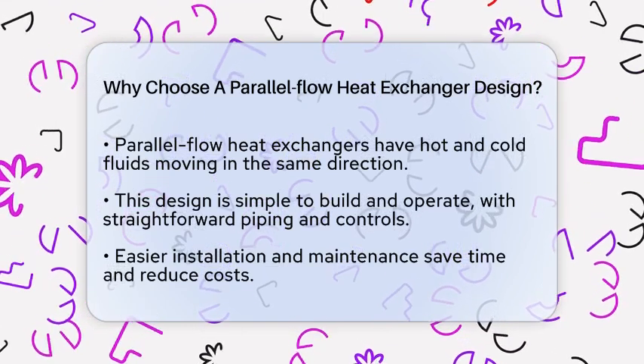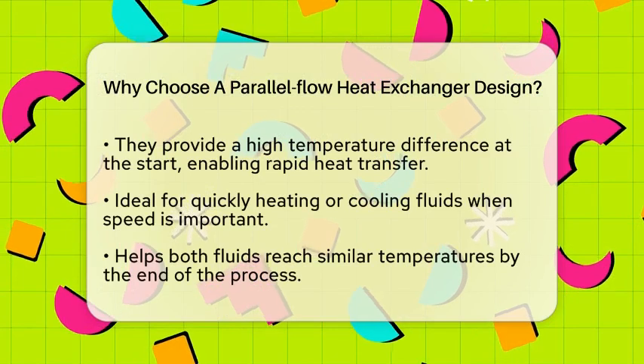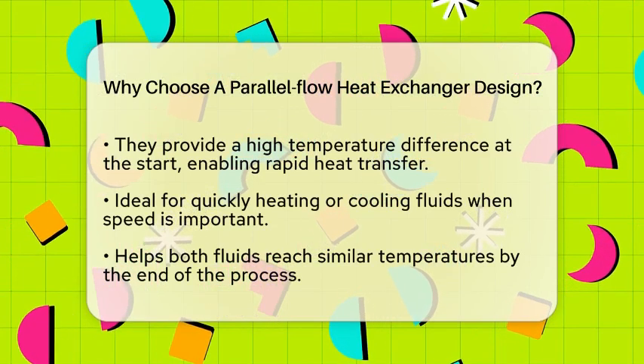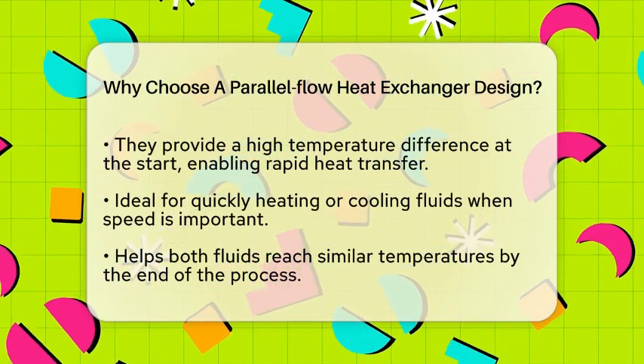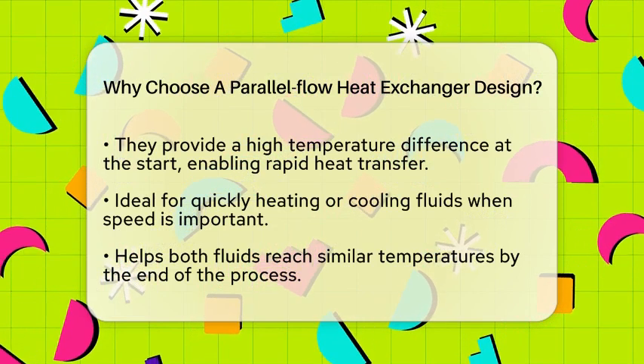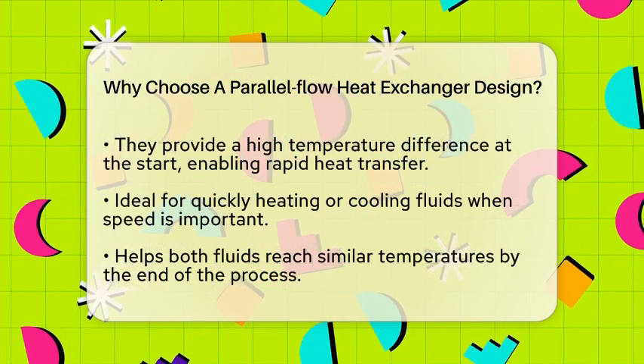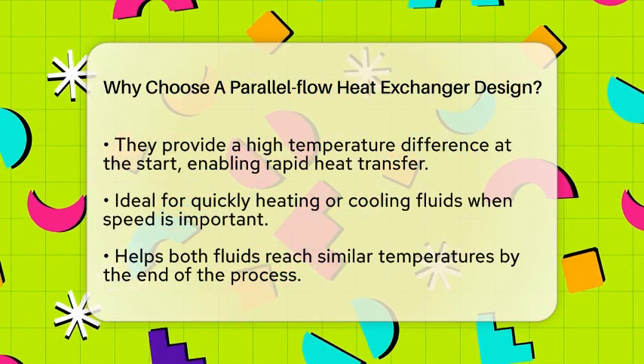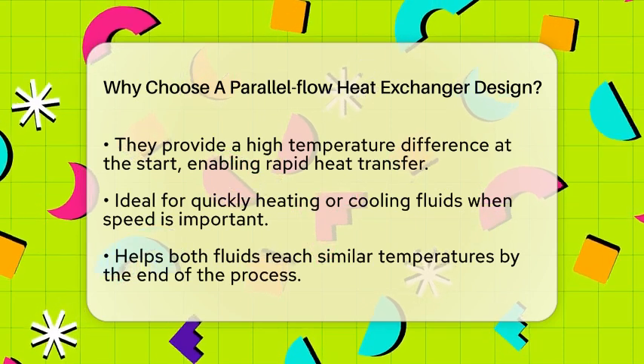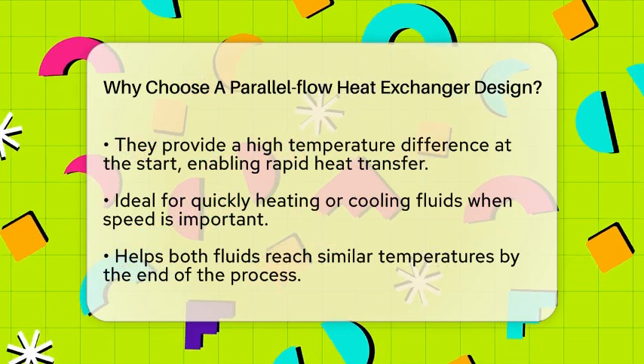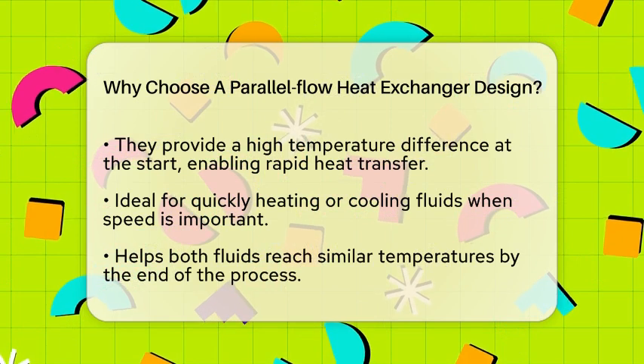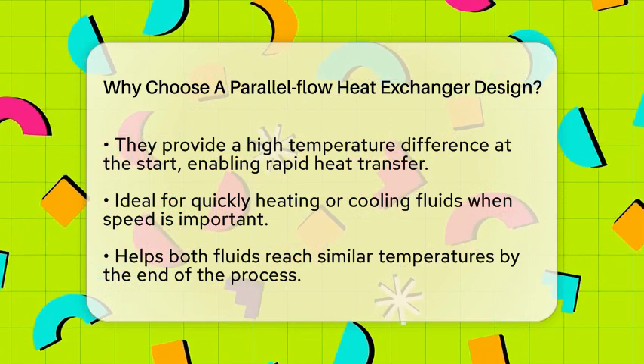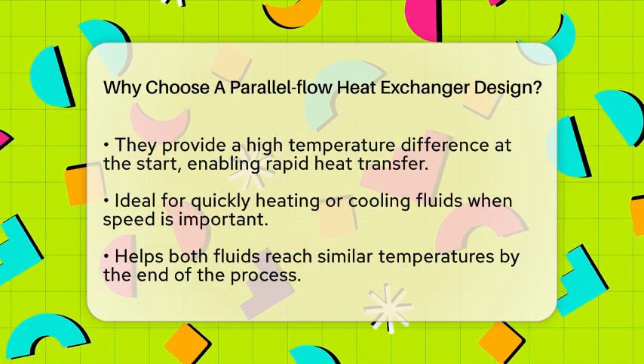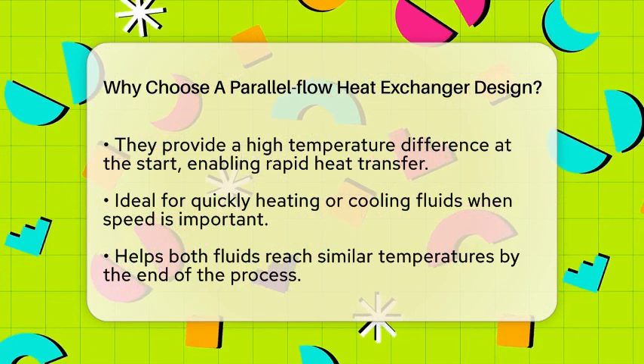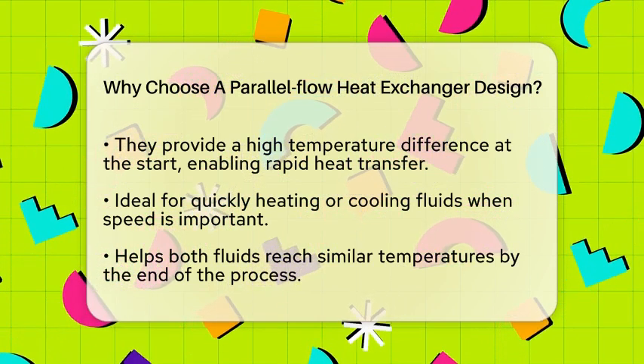One big advantage of parallel flow is the high temperature difference at the start. When the fluids enter the heat exchanger, the hot fluid is much hotter than the cold one. This large temperature gap causes heat to transfer quickly at the beginning. If you need a rapid change in temperature, like quickly cooling a hot liquid or heating something fast, this design is very effective.